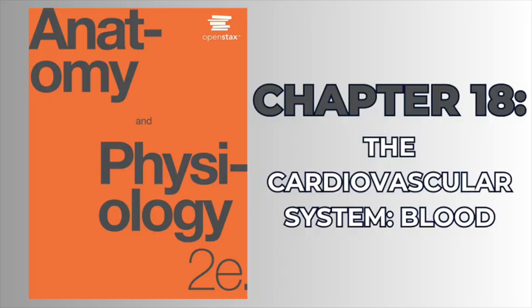In determining oxygenation of tissues, the value of greatest interest in healthcare is the percent saturation. That is, the percentage of hemoglobin sites occupied by oxygen in a patient's blood. Clinically, this value is commonly referred to simply as percent sat. Percent saturation is normally monitored using a device known as a pulse oximeter, which is applied to a thin part of the body, typically the tip of the patient's finger. The device works by sending two different wavelengths of light, one red, the other infrared, through the finger and measuring the light with a photodetector as it exits.